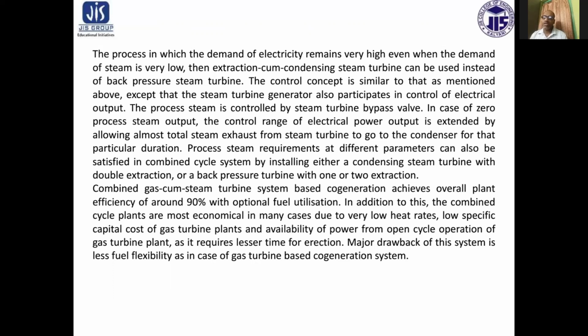Process steam requirement at different parameters can also be satisfied in a combined cycle system by installing either a condensing steam turbine with double extraction or a back pressure steam turbine with one or two extractions. Combined gas cum steam turbine based cogeneration achieves an overall plant efficiency of around 90% with optimal fuel utilization.